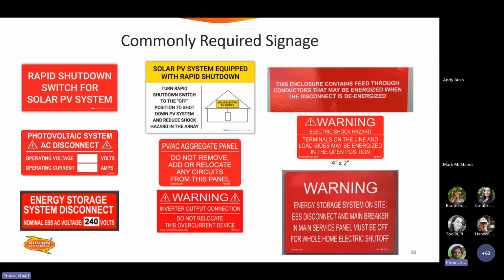So that's essentially like if you're doing a partial home backup and you have to get access to conductors that you want to back up, but you can't move them out of that existing main panel. What that means is somebody's going to shut off that main disconnect and you're still going to have conductors in there that are energized from wherever your transfer switch is. So that's how we handle that label to warn people that, hey, you turn the main disconnect off, you still might have some live wires in here. The other ones are pretty straightforward. I think you'll understand those.